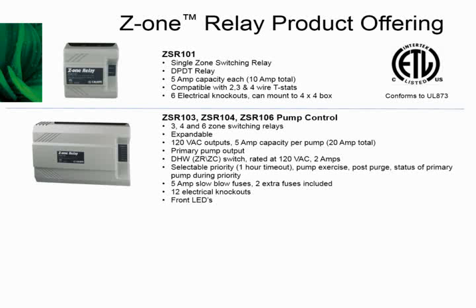Up and beyond the zone control pumps, we also offer a primary pump output and a domestic hot water switch, or ZRZC switch, because it's rated up to 120 volts and 2 amps. So on some of those systems out east, like the Levesque brothers showed me, this is a perfect match for those types of controls. It has selectable priority, and there's a 1-hour timeout on that, so it can prevent freeze-up. Pump exercise is selectable, and that works by if there is no action by that pump for 72 hours, it'll run it for 3 seconds. And each one of the pumps is independently timed on that. So it's not just all of them get it or all of them don't. Each pump is individual.